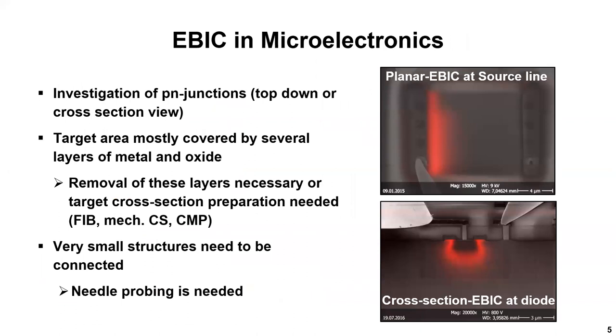If we talk about EBIC and microelectronics structures, we could have a top-down imaging or a cross-section view. For the top-down view, the covering metal layers often have to be removed by chemical polishing or focused ion beam assisted methods. This source depletion zone of a high voltage transistor could be visualized after a CMP preparation down to contact level. For cross-section investigations, mechanically prepared samples or focused ion beam techniques can be used. This diode structure was investigated after mechanical cross-section preparation. A local connection of the prepared structure is often necessary and typically realized by probing at contacts or at metal lines.